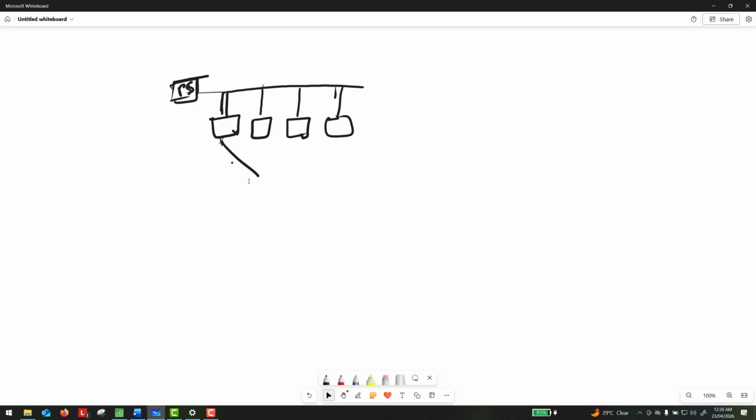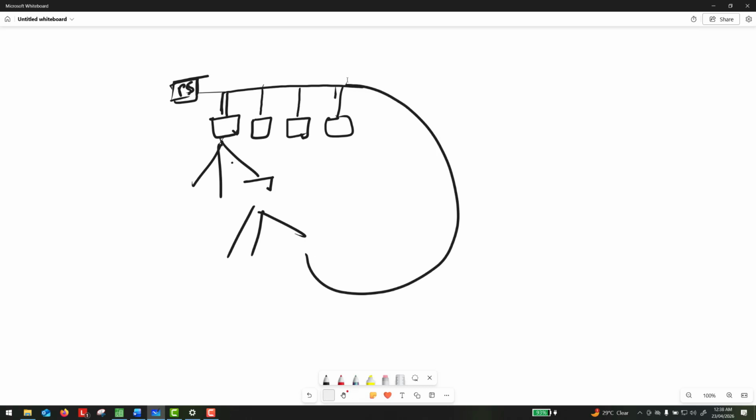So again, those three devices can again split into three. So it can grow exponentially. Okay, so there is nothing stopping you. The only thing that you should not do is you have a device here, and this device should not come back here. That's the only thing you should not do. Okay, so a loop is not allowed in KNX. So all the devices have to be ended there.